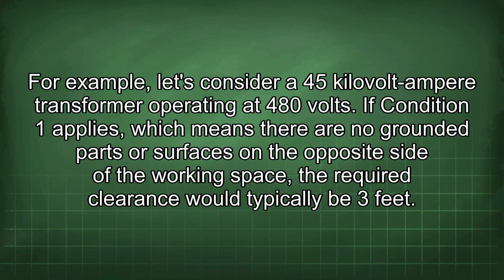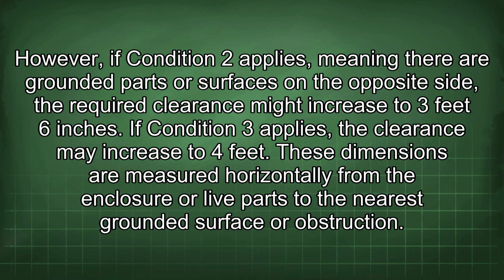clearance. For example, let's consider a 45 kilovolt-ampere transformer operating at 480 volts. If condition 1 applies, which means there are no grounded parts or surfaces on the opposite side of the working space, the required clearance would typically be 3 feet. However, if condition 2 applies, meaning there are grounded parts or surfaces on the opposite side, the required clearance might increase to 3 feet 6 inches. If condition 3 applies, the clearance may increase to 4 feet. These dimensions are measured horizontally from the enclosure or live parts to the nearest grounded surface or obstruction.